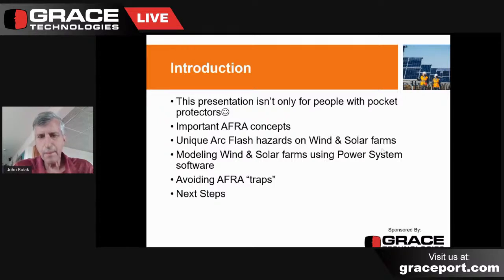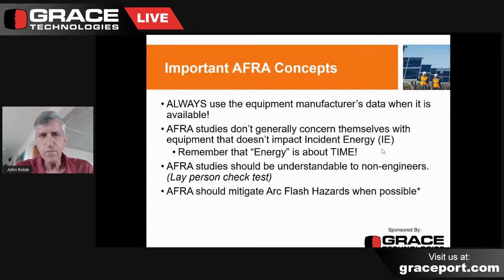And then we'll talk about some next steps, and hopefully the sum of all that, as I said, will be helpful for you. So some basic concepts. One thing that I strongly recommend, and this is also related to what is available: rather than doing calculated values, for example, for the short circuit current that can be outputted by a generator or whatever, always get the information from the manufacturer if you're able, and use that information. OSHA always defers to the manufacturers when they have multiple options, and that would be a good suggestion for us as well.